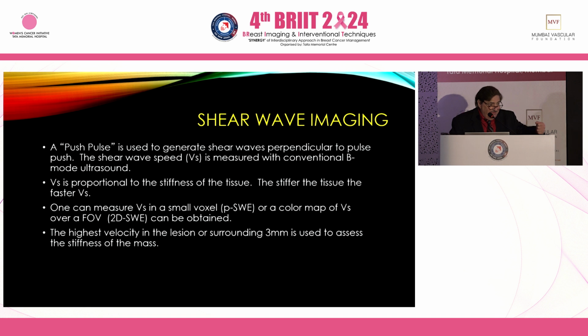Creates a big boom, and then that creates the shear waves. It's important to realize that the push pulse only generates the shear waves. It's B mode that tracks the shear waves and calculates the shear wave speed. So if you have an artifactual B mode image, you're going to get an inaccurate shear wave. So again, important thing to remember.